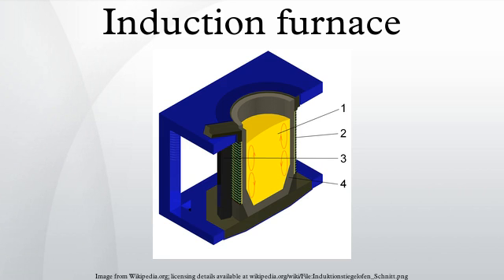An induction furnace consists of a non-conductive crucible holding the charge of metal to be melted, surrounded by a coil of copper wire. A powerful alternating current flows through the wire. The coil creates a rapidly reversing magnetic field that penetrates the metal. The magnetic field induces eddy currents, circular electric currents, inside the metal, by electromagnetic induction.